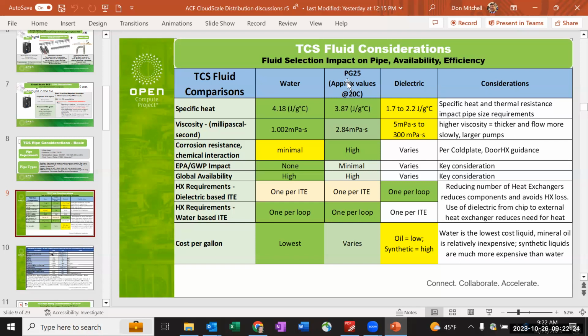If you run conventional door heat exchangers, they've got generally large tubes in them, and they can handle all kinds of crap in the coolant and just don't care. Depending on the kind of cold plate you run, if it's a tube soldered to a plate, an eighth inch tube or something like that, they don't care about how much crap runs through there. So there's pretty much no requirements on how crappy the coolant can be, other than anti-corrosives and biologics and all that other stuff you put in the coolant.